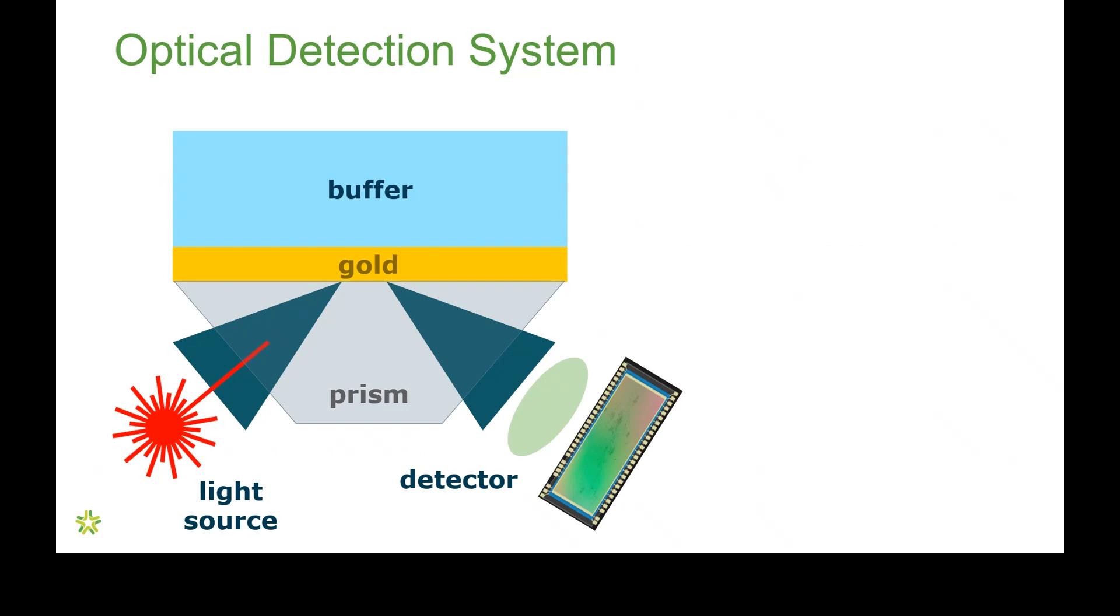This is the optical detection system for the Carterra LSA biosensor. The heart of this is the gold layer. On one side of the gold layer is buffer, through which we flow analyte, and ligand is attached to that gold layer. On the other side of the gold layer is a glass prism. Light is shown through the glass prism, and it's reflected and measured by a detector.